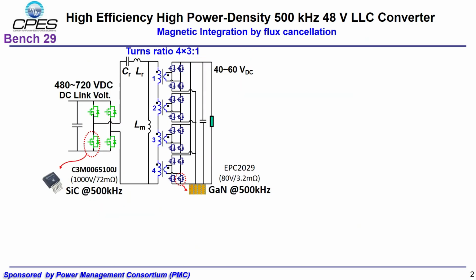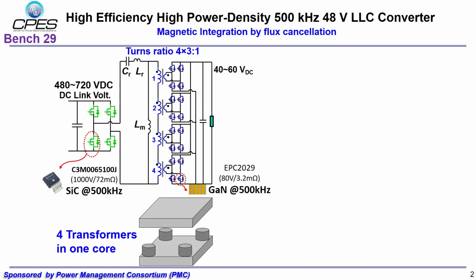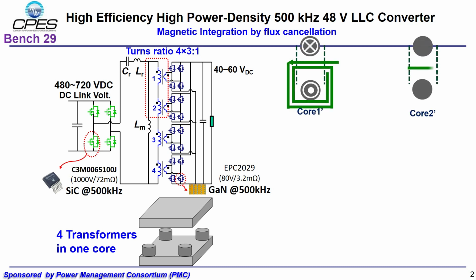The four elemental transformers can be integrated into a single magnetic core by means of flux cancellation. Take two elemental transformers as an example. Here shows the flux inside the round-shaped leg and the primary side winding current direction.